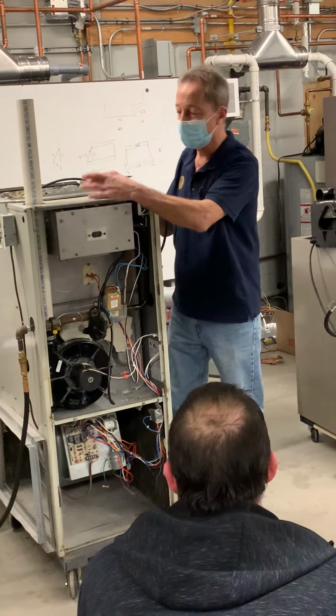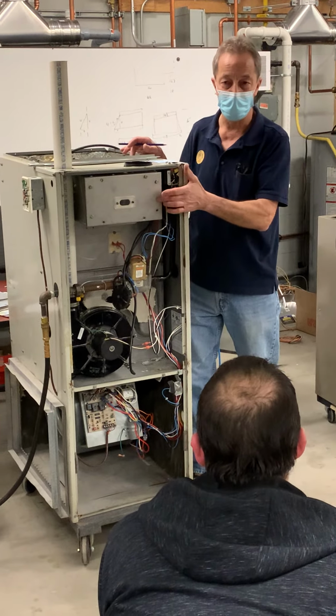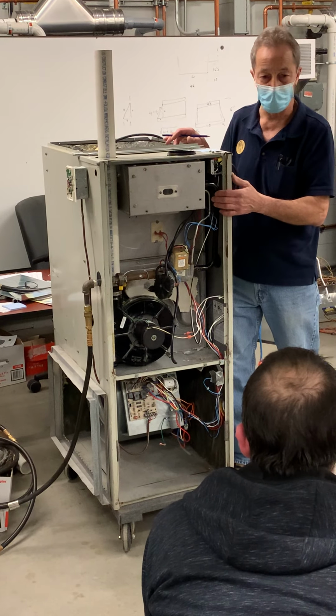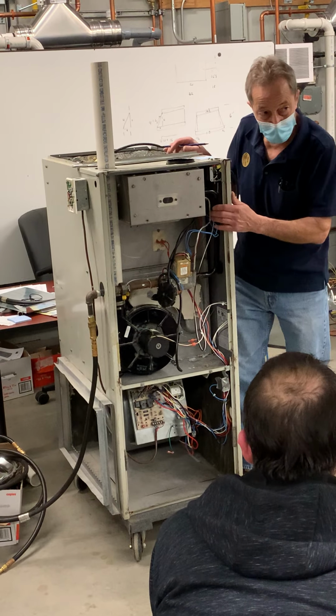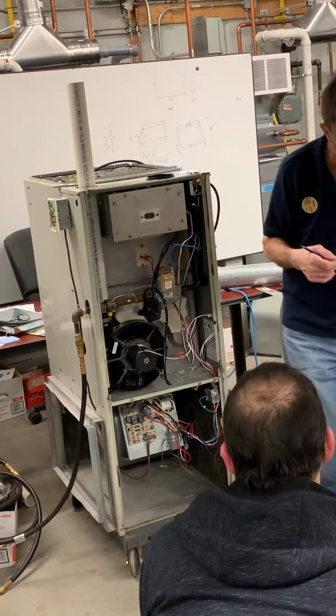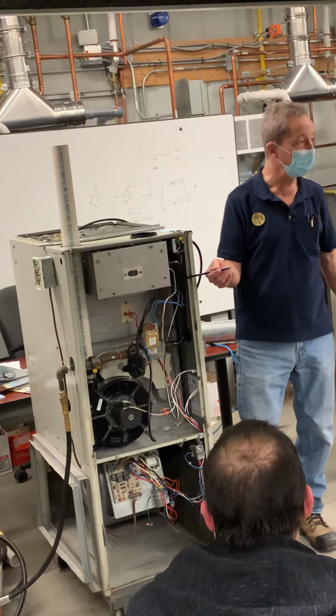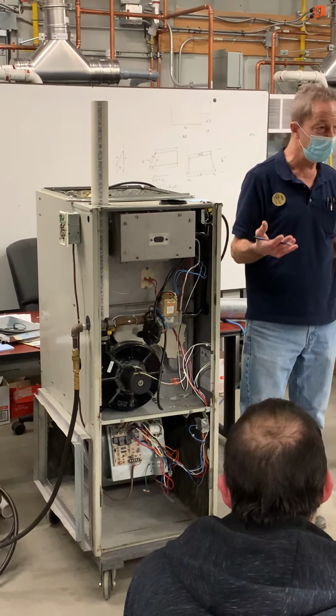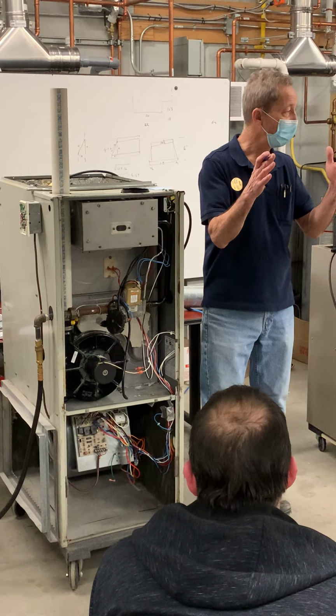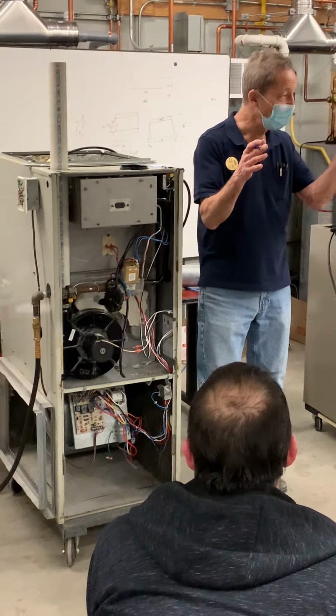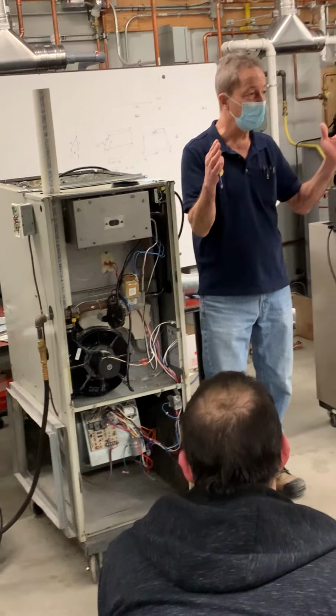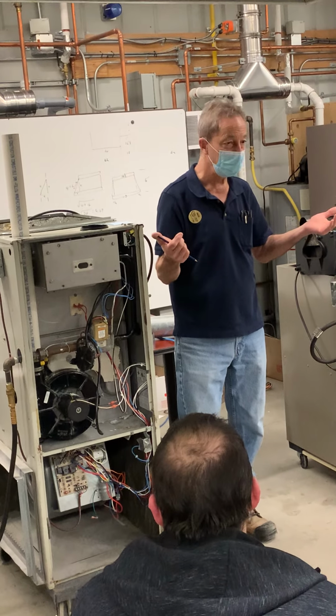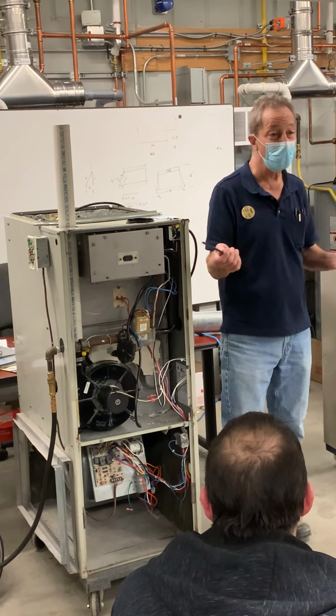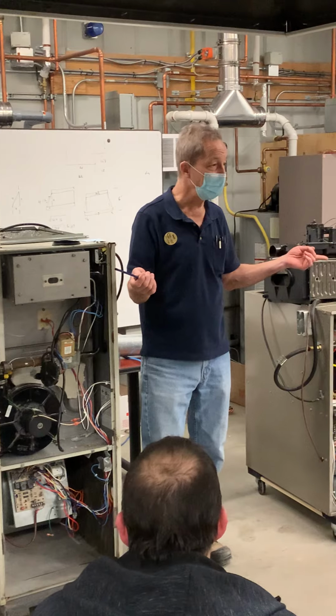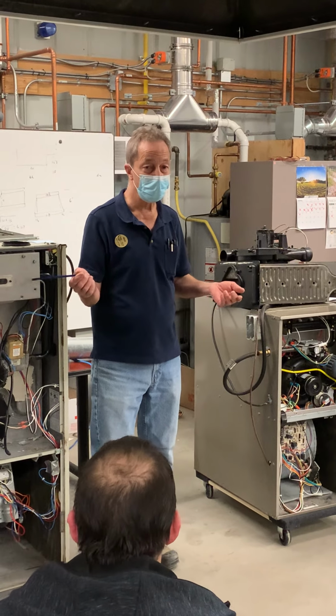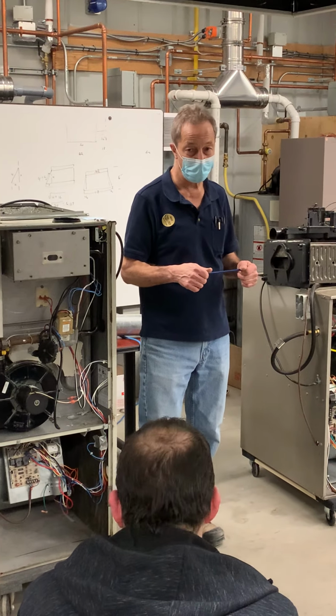If this is negative, because I've got a long intake pipe, I could have negative 1 inch here. If I've got negative 1 inch, and my manifold pressure is normally what pressure? What's a normal manifold pressure for a furnace? 3.5, right? So normal manifold pressure is 3.5. If it's going into an area here which is negative 1 inch, what's my differential? 4.5. One's positive 3.5, one's negative 1. The net differential is 4.5, so it's going to overfire. If it overfires, now I've got a new set of problems, right? It could go off on the flame rollout, it could go off on the high limit, but that's due to overfiring versus a blocked secondary heat exchanger.